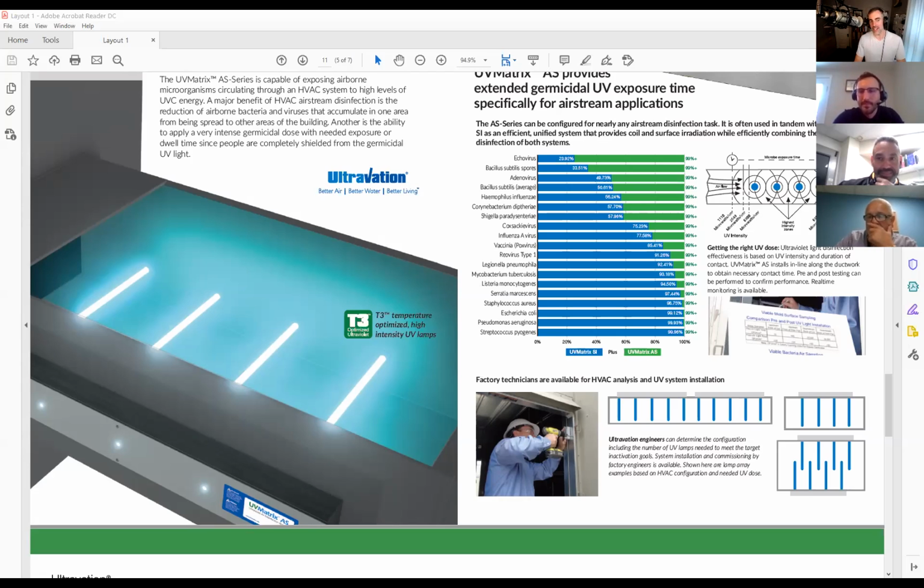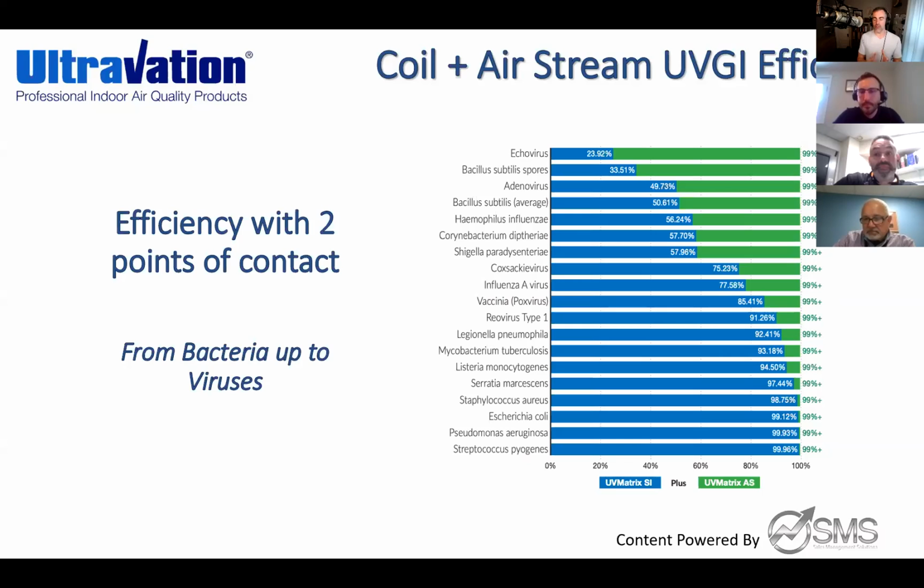But back in the day, this is probably 8 years ago, they were concerned with the black spores. It was very inconsistent. Some of the rooftop units had nothing inside of them. Other rooftop units had black spores on the outside casings across from the coil, but it was not consistent across all equipment. It was very interesting. It's the same experience that I have specifically working on malls. The closer you get to where they're actually working on the food court, that's where you get more mold spores. The other side, totally different. So it's absolutely understandable.